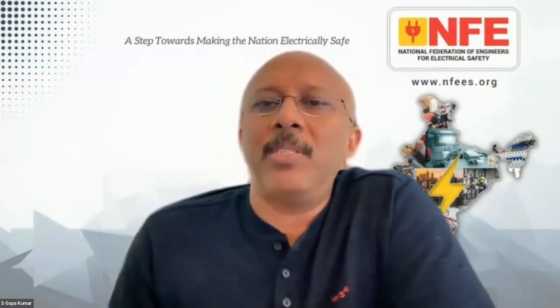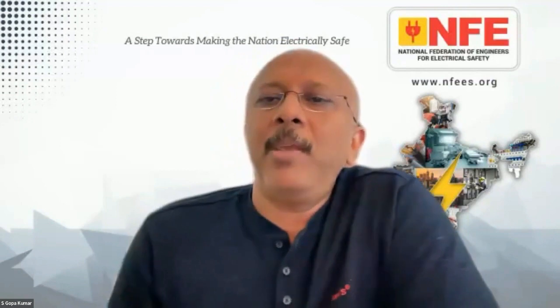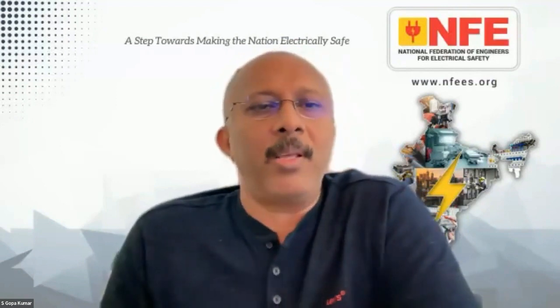The first question is from Mr. Sanjay Mulai, whether supplementary equipotential bonding will help to clear a fault. So there's a yes and no in that. It will help to equalize potentials. So it will give you equipotentials between two conductive or extraneous parts, not necessarily help clear the fault unless that link creates a lower impedance. We used to, in bathrooms, which is a high risk in houses, cross bond, supplementary bond, everything, the lights, the radiators, the taps and everything, to try and ensure where there was a high risk in bathrooms that there were equal voltages.